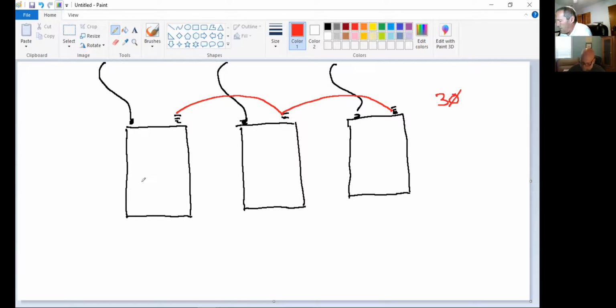Remember, if I have 100 amps here, 150 here, and 100 over here, that's load imbalance. Well, what path does load imbalance follow? The neutral, correct? We talked about that before. Yes. So what's going to happen here is current flow is going to go this way, and it's going to go this way, that imbalance is going to go both directions. And then these two other transformers are going to help share this load imbalance happening in the center. That's why we have a floating neutral on closed delta. Remember that. All right, so let's control Z, get rid of all this.